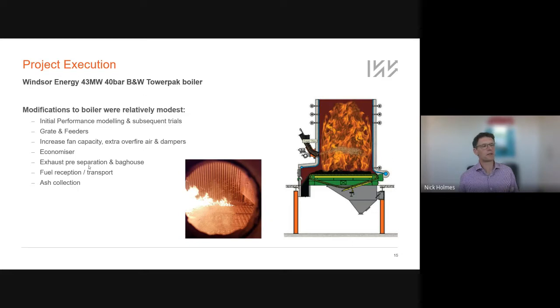The bottlenecks were predominantly around the fan capacity, the ratio of combustion air and overfire air, and how you control that. The amount of air is higher, so the cleanup system needs to be addressed in terms of a larger baghouse, additional pre-separation. I think there were also some other elements around the grate and the economizer that were coming to the end of life. So that sort of rolled into the project. Different fuel transport and reception. So we could utilize the existing equipment in principle, but with some upgrades. And the ash system is quite different, significantly less ash and different characteristics of how it's managed.